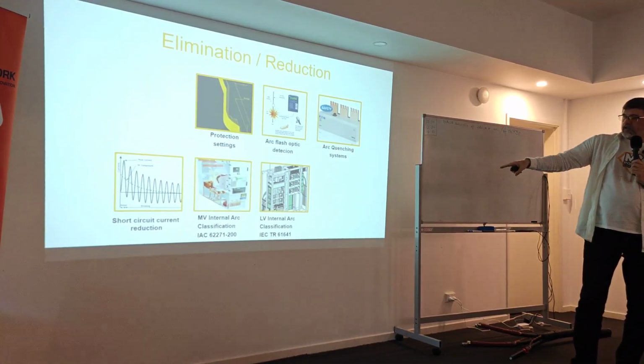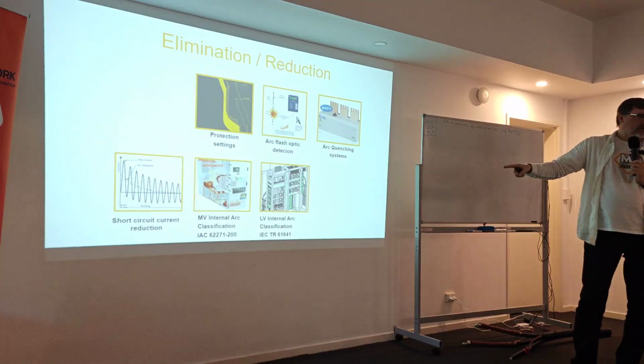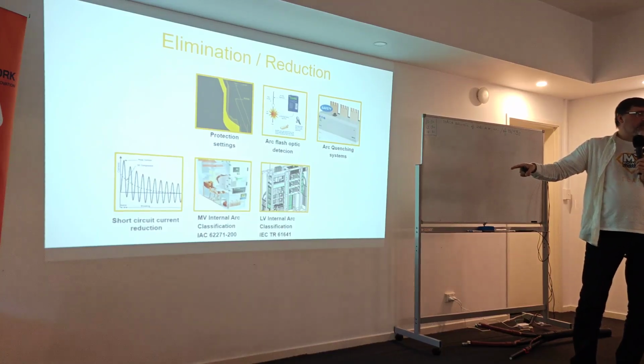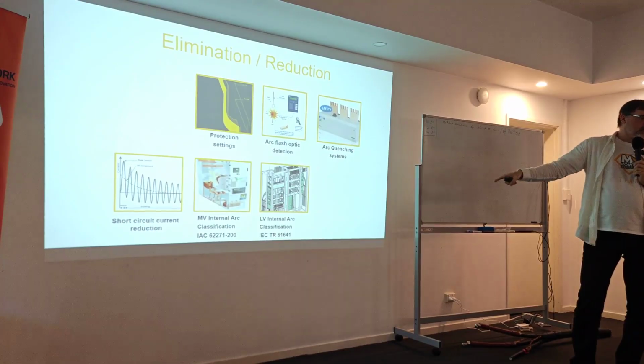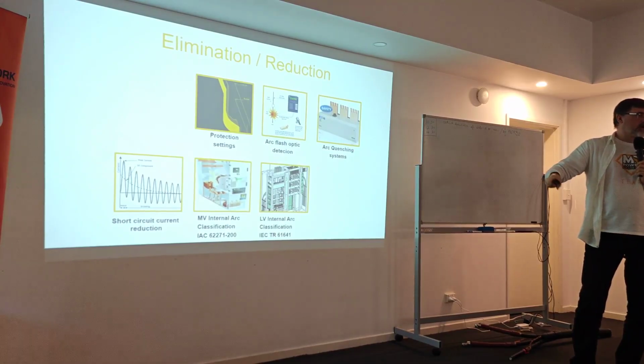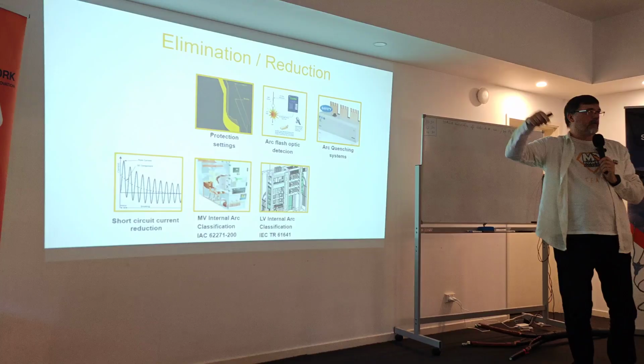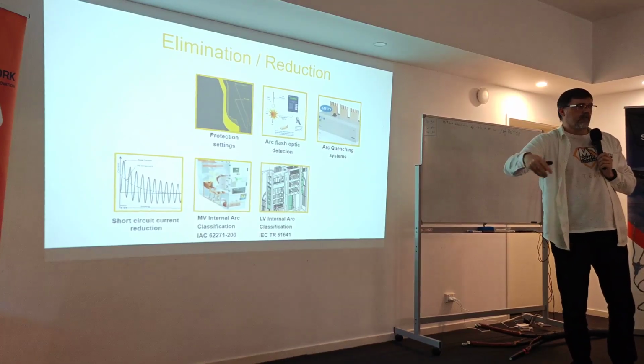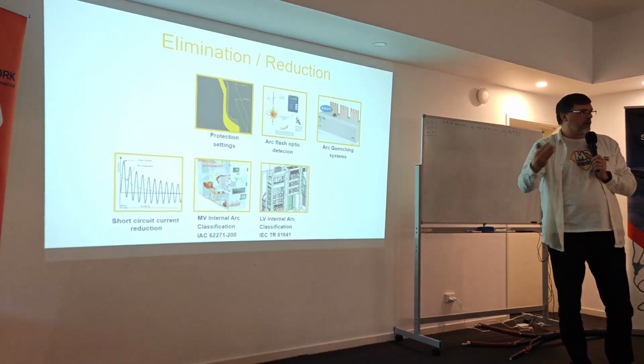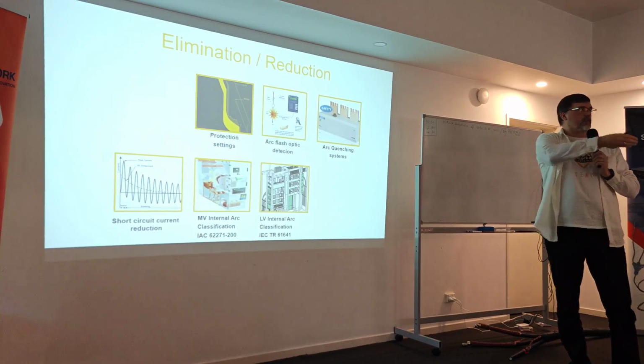Internal classification, I think you also follow, everyone almost follows IEC standards for it. Most of the medium voltage switches will be internal arc classified, so they will be tested for the arc which will happen inside the panel, yeah? In case of switching, whatever failure, breaker, cable failures, and it should stay inside the panel.